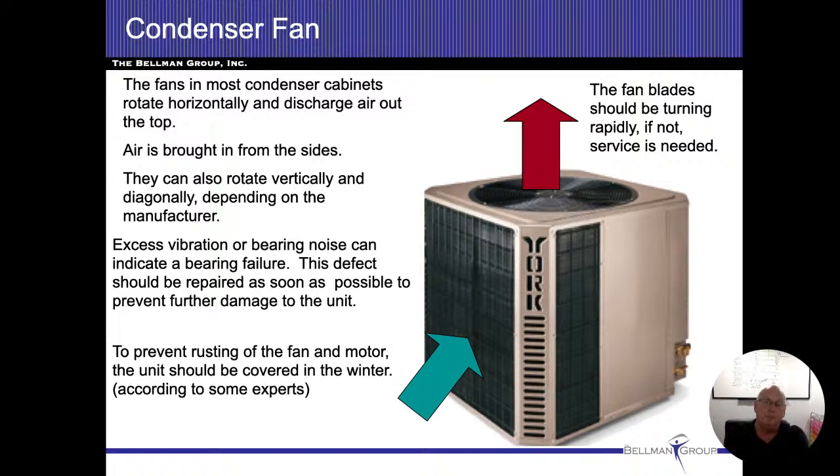So for the most part, the fans are going to blow the air upwards. So the outside air is going to come through the coils, and then it's going to be blown upwards, all right? They can also rotate vertically and diagonally depending on the manufacturer. That's true. You should hear a hum. You should hear minimal vibration coming out of it. But it shouldn't be loud. It shouldn't be rattling. It shouldn't be shaking. Those are all things that could tell us that we've got some bad bearings or something that's getting to the end of its lifespan.